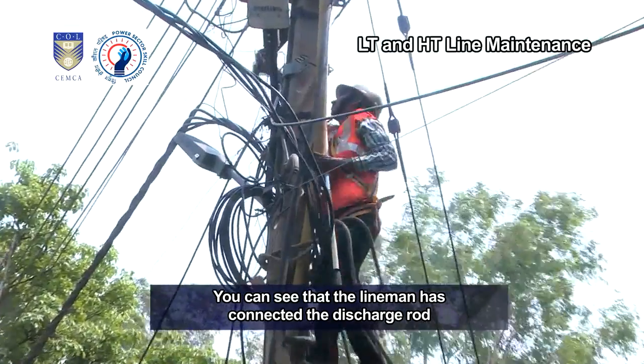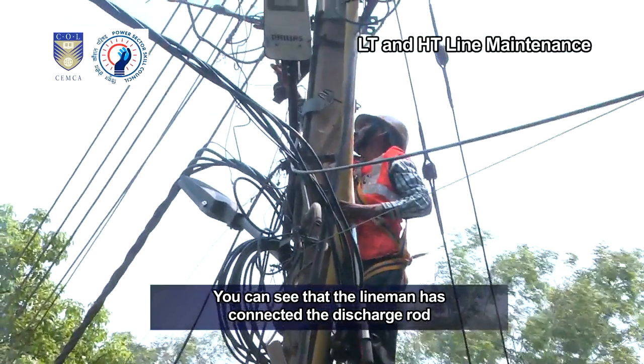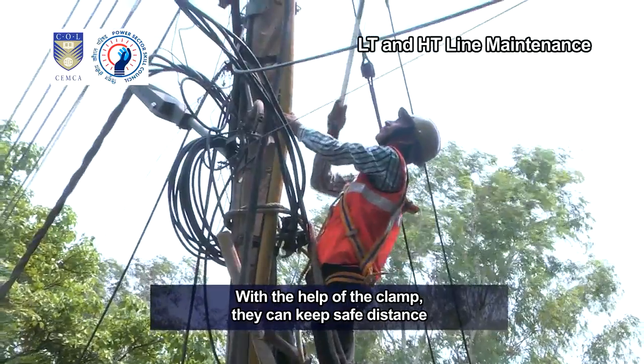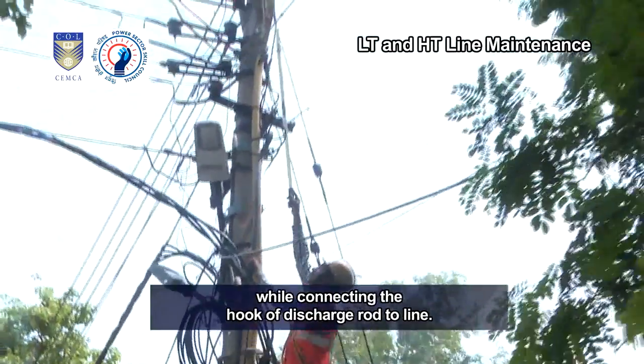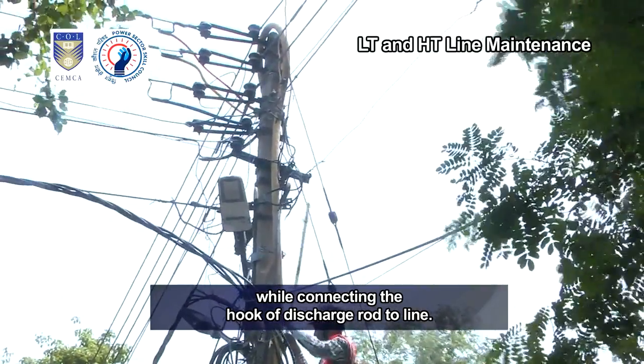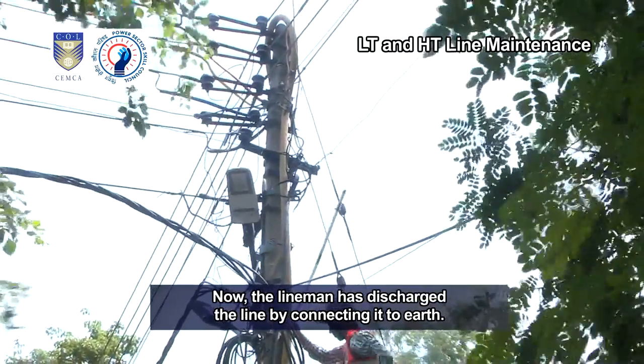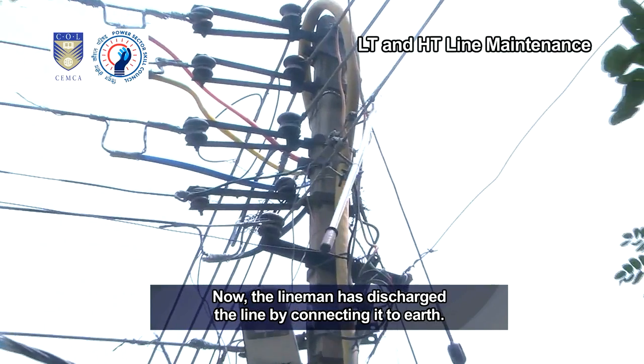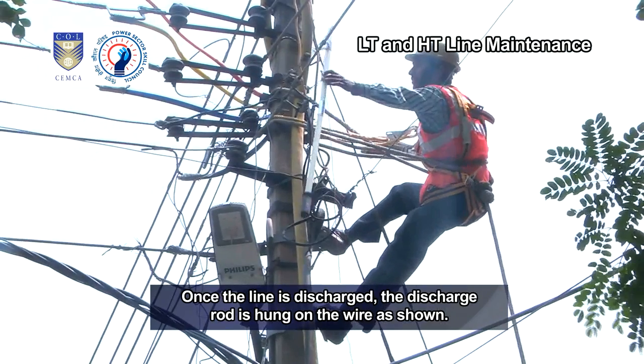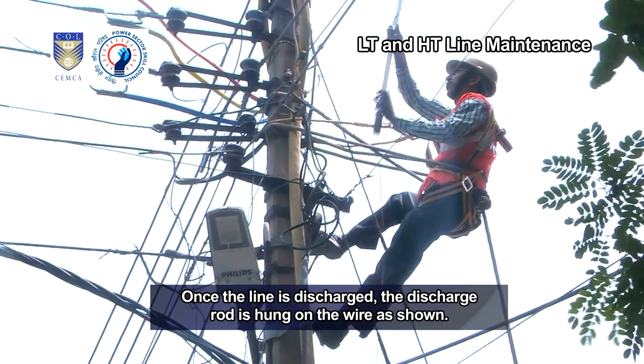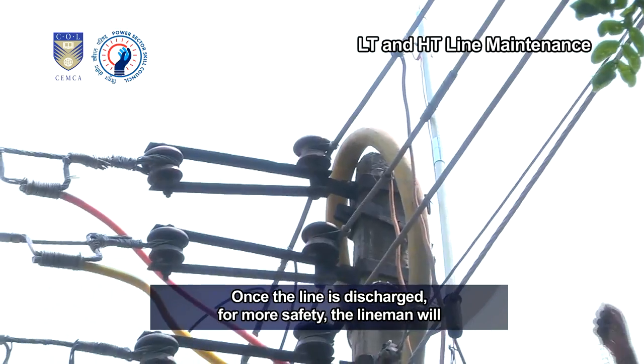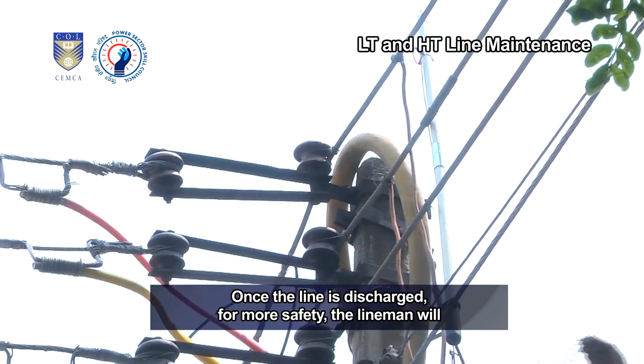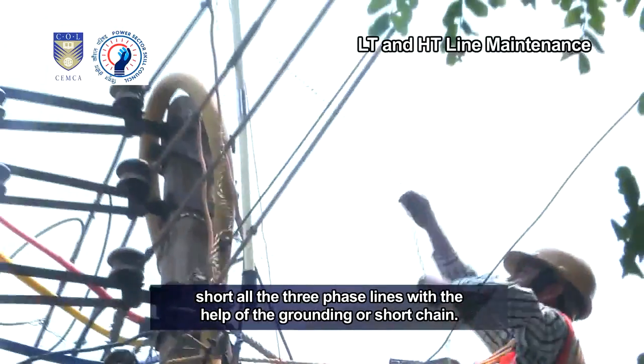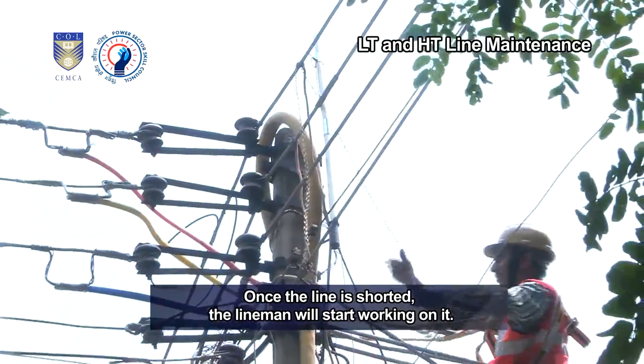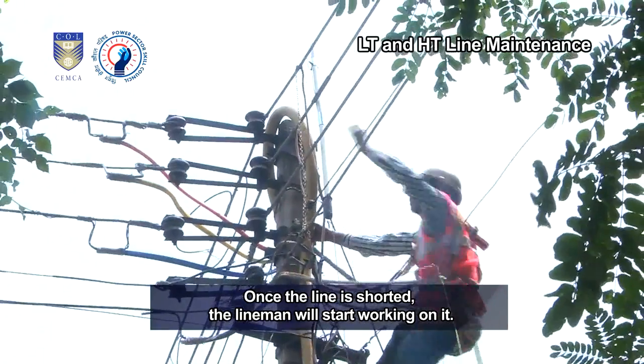You can see that the lineman has connected the discharge rod earth lead with a clamp. With the help of the clamp, they can keep safe distance while connecting the hook of discharge rod to line. Now, the lineman has discharged the line by connecting it to earth. Once the line is discharged, the discharge rod is hung on the wire as shown. For more safety, the lineman will short all the three-phase lines with the help of the grounding or short chain. Once the line is shorted, the lineman will start working on it.